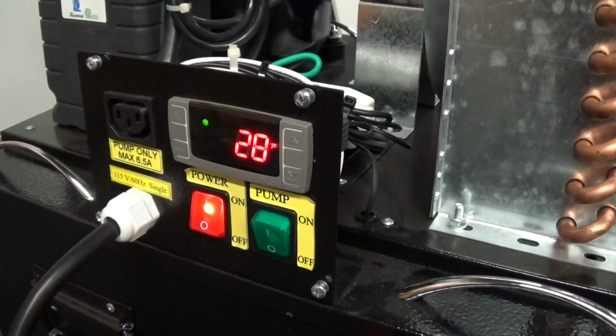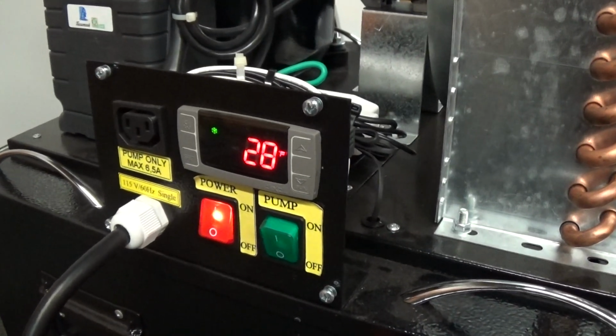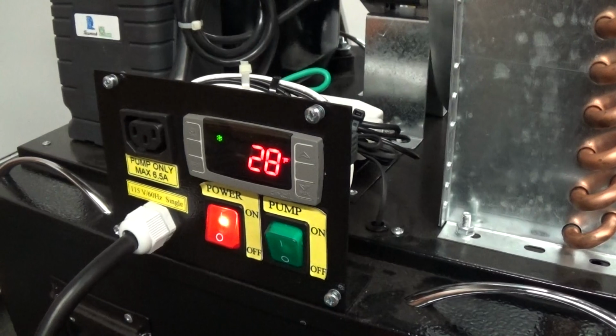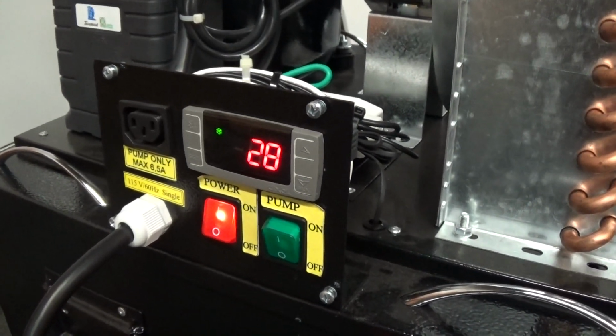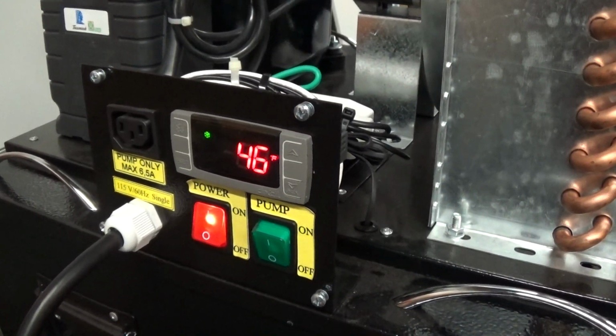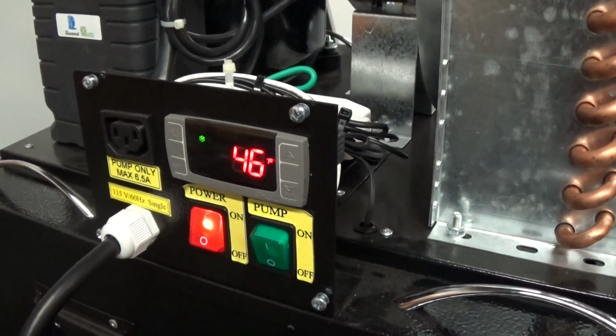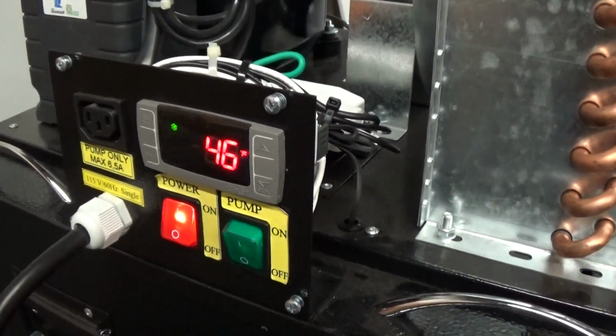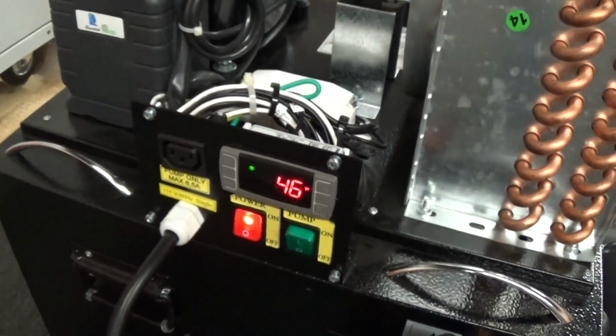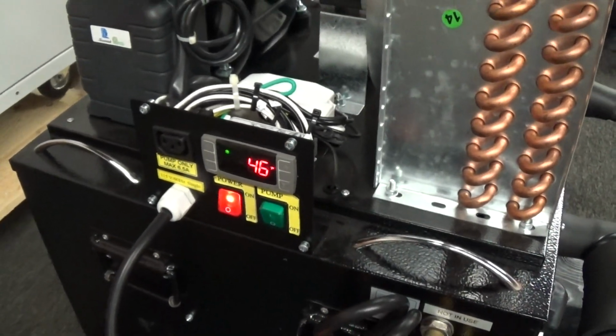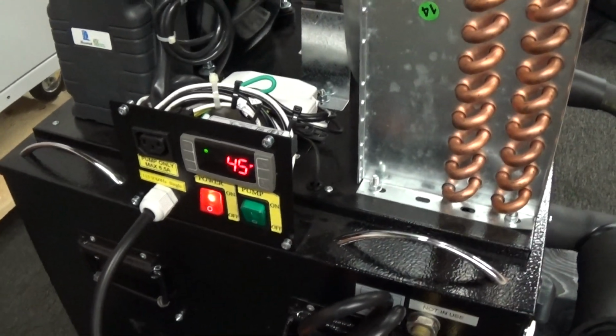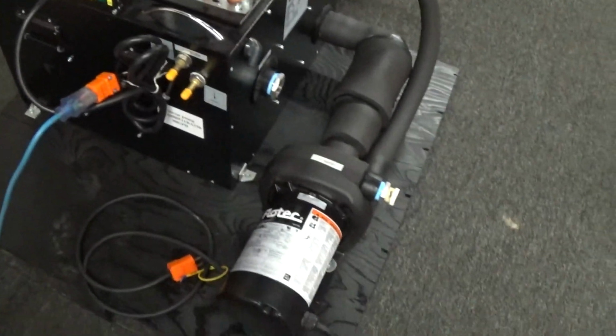It's flashing, so I can adjust it up or down. If I don't touch anything, after several seconds, it's just going to default back to what the process value is, which is right now 46. So it slowly starts cooling. We don't have any glycol in the tank right now. This is just for demonstration because we have been running it extensively with glycol in it. Conversely, you never want to ever, under any conditions, run your glycol pump dry.